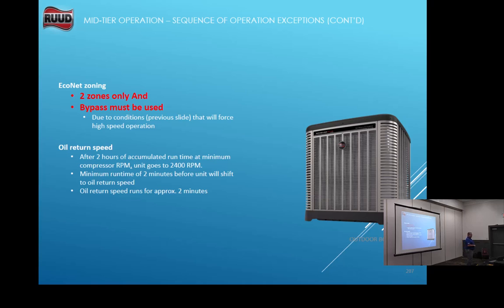And I'm sorry, but most people in our industry do not know how to do zoning. And RUUD has recognized that fact and says we want to protect this compressor from liquid flood back. So we're still going to give, you only can put 2 zones and you have to have a bypass. You know, that still comes down to the contractor. If he puts a 5-ton system in and that homeowner says, well, I got a bonus room. Oh, I can zone it. And you're going to put 5 tons of air on 2 zones and have one 12-inch duct or 10-inch duct run into 2 outlets on a 400 square foot room. You still have to size the duct correctly, okay? You still have to size the zones correctly.